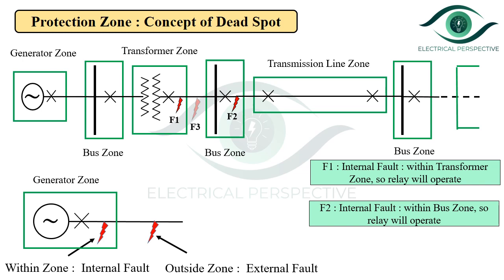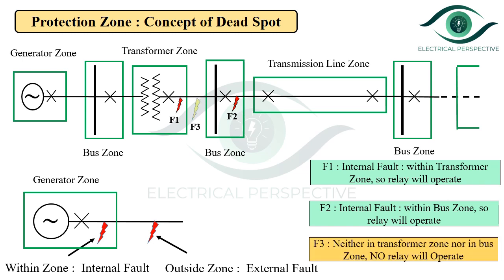Now consider fault F3. Is F3 in the transformer zone? No. Is it in the bus zone? Again, no. So F3 is neither in the transformer zone nor in the bus zone, meaning no relay will operate. Even though it is a fault, since it does not fall under any zone, no relay will operate and it will not be cleared by the protection system — and this may damage the healthy parts of the system. The unprotected part is called a dead spot or dead zone. As shown in the figure by the pink color line, these unprotected parts are called the dead zone.